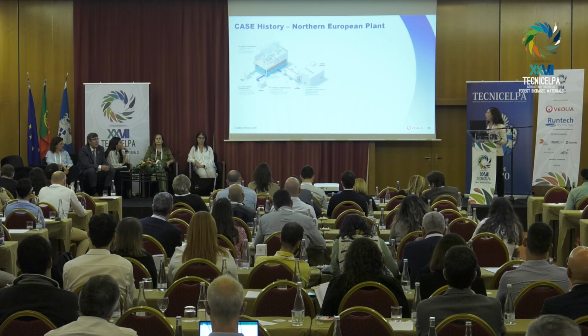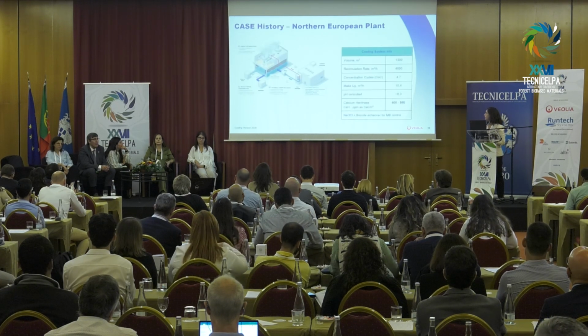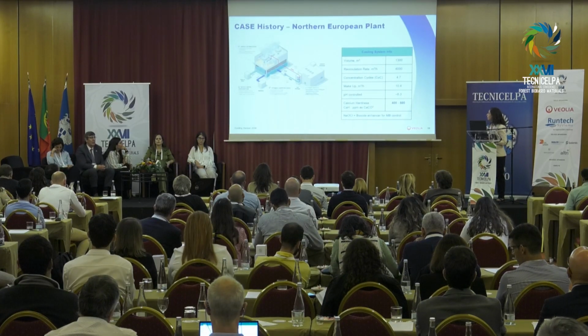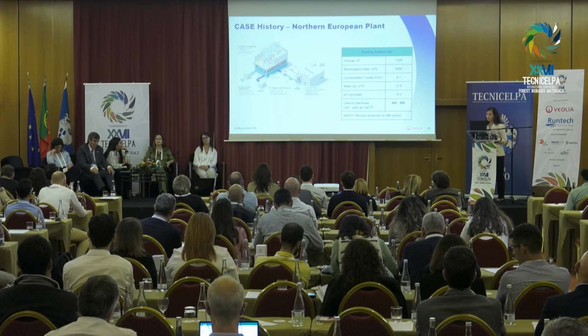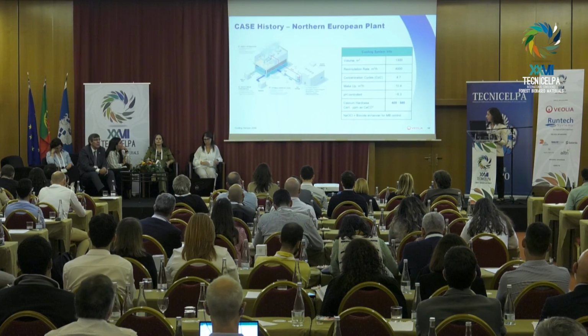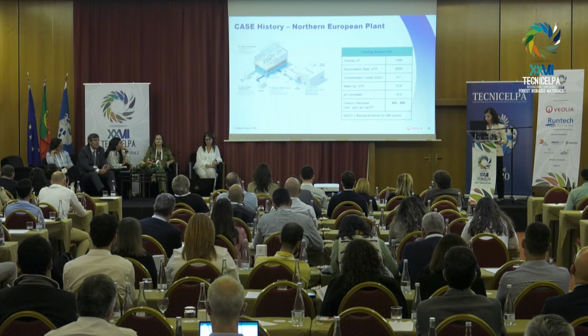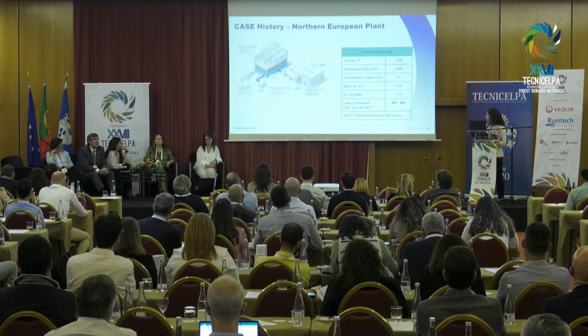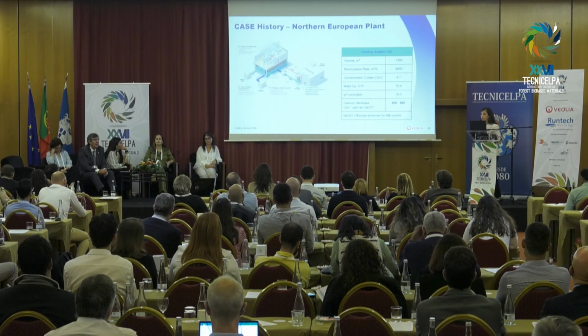Let's see how their circuit was. They had a cooling tower with 1,300 cubic meters, and these are all the data with the recirculation rate, flow, concentration cycles of 4.7, which is not so bad for a cooling system.